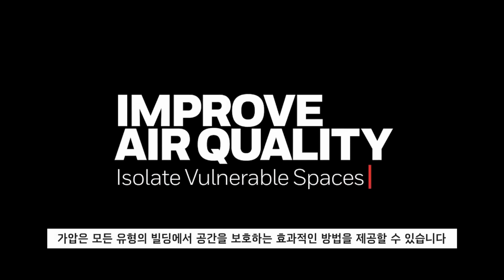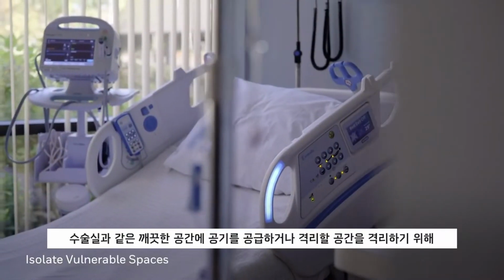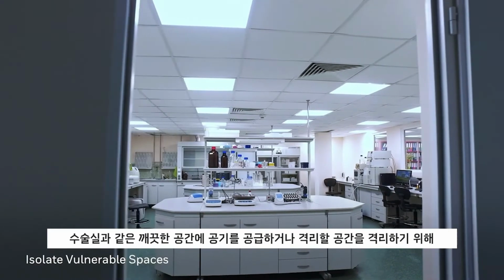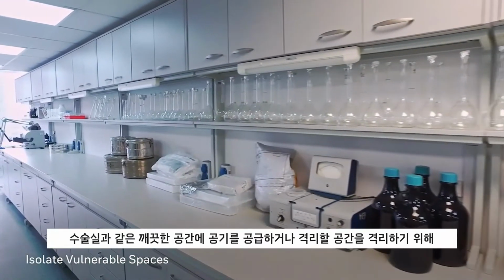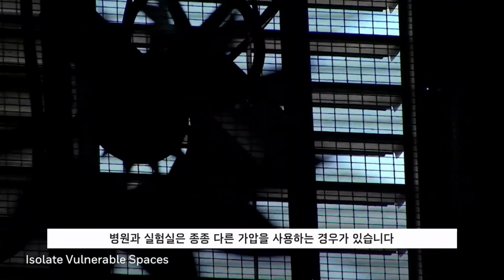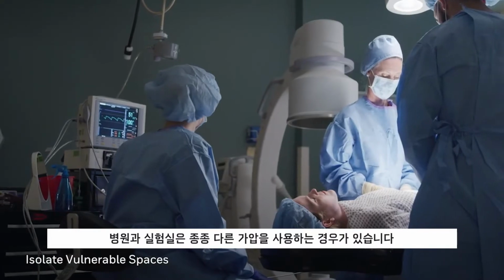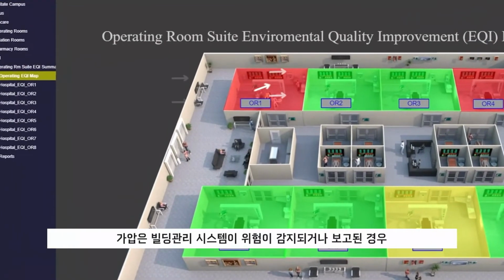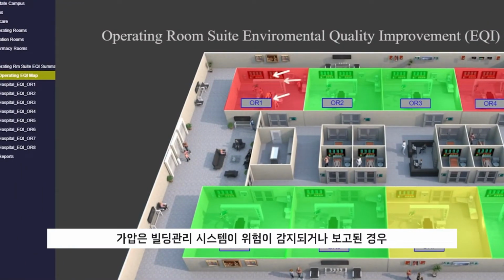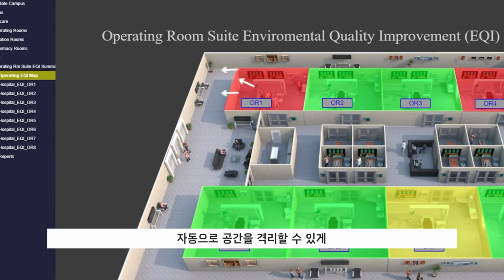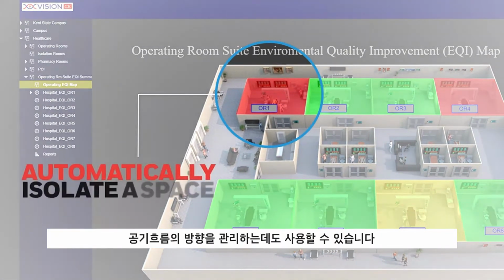Pressurization can provide an effective way to protect spaces in any type of building. For instance, hospitals and labs often use differential pressurization to isolate a quarantined space or contain air in a clean space, like a surgical suite. Pressurization can also be used to manage the direction of airflow, enabling your building management system to automatically isolate a space when a hazard is detected or reported.